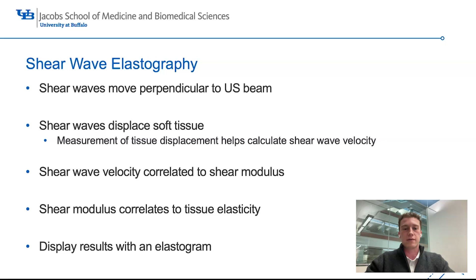And from those displacements, which are different in different types of soft tissue, so tendon will react differently to the shear wave, fascia will react differently to the shear wave, muscle will react differently to the shear wave. From the amount of displacement of those tissues, you can calculate the shear wave velocity. Through Sarvazyan's work, the shear wave velocity can be correlated to the shear modulus through an equation, which we'll get to on the next couple of slides. It's that shear modulus that is the correlate to the tissue's elasticity. And then finally, the shear modulus can be mapped in color and give you a color ultrasound image to describe the stiffness of any given tissue.